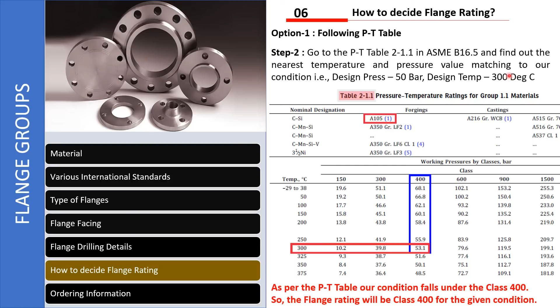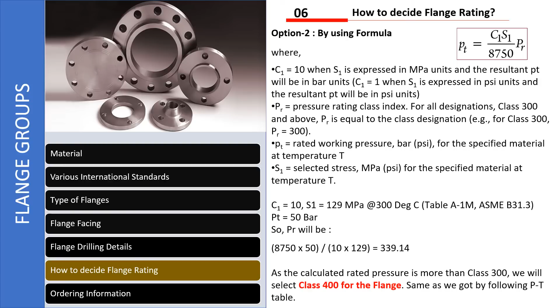Now let us look at option 2. Here we have a formula given in 16.5 Appendix A, with C1, S1 and PT. C1 is 10, standard; S1 is the allowable stress; and PT is the design pressure, which we are taking as an example. Once we put in these values, PR can be calculated. Once we put these values in this formula, we get 339.14, which is more than class 300. Hence we can say this belongs to class 400. This is the same information we checked in the PT rating table in option 1. So both options give us class 400. This is how we can calculate the flange rating of any flange.